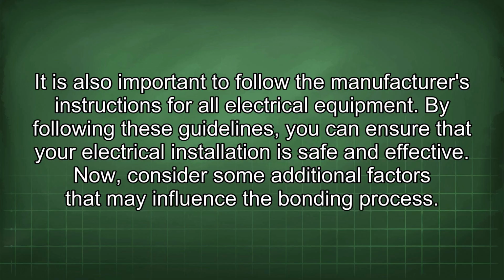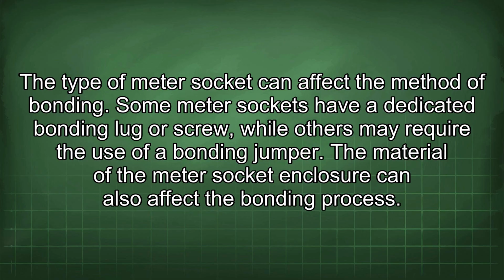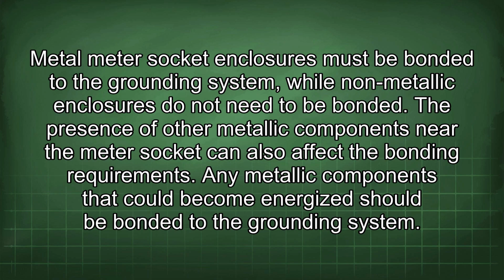Now consider some additional factors that may influence the bonding process. The type of meter socket can affect the method of bonding. Some meter sockets have a dedicated bonding lug or screw, while others may require the use of a bonding jumper. The material of the meter socket enclosure can also affect the bonding process. Metal meter socket enclosures must be bonded to the grounding system, while non-metallic enclosures do not need to be bonded. The presence of other metallic components near the meter socket can also affect the bonding requirements. Any metallic components that could become energized should be bonded to the grounding system.